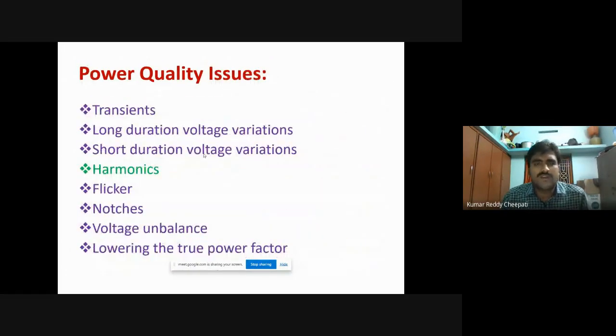So in general, these are the various power quality issues which affect the quality of supply: transients, long duration voltage variations, short duration voltage variations, harmonics, flicker, notches, voltage unbalance, and lowering of the true power factor. As you know, transients usually occur due to the sudden switching on and the sudden switching off of loads. Transients are of two types: unidirectional transient and bidirectional transient.